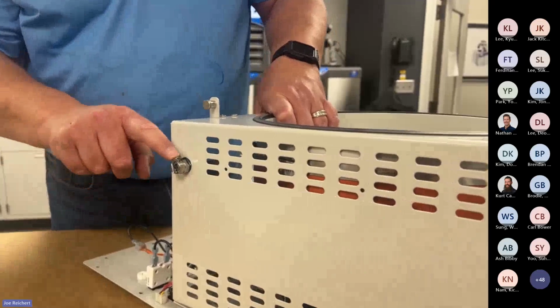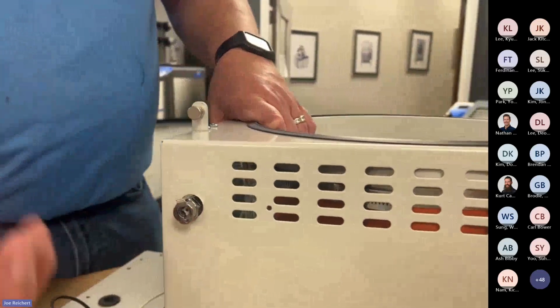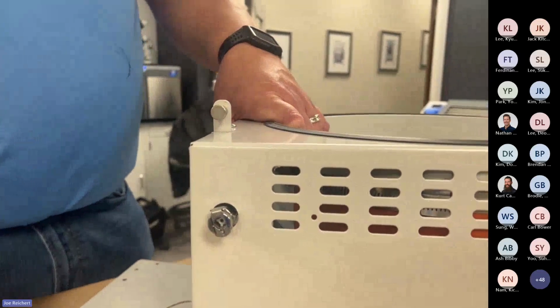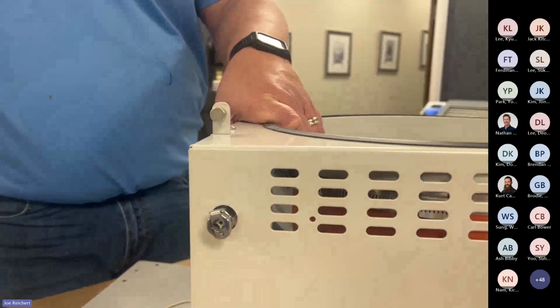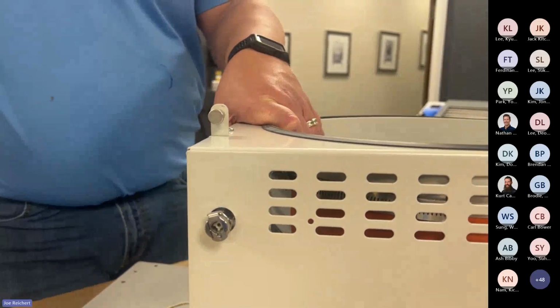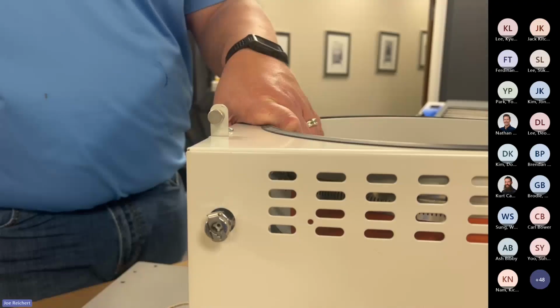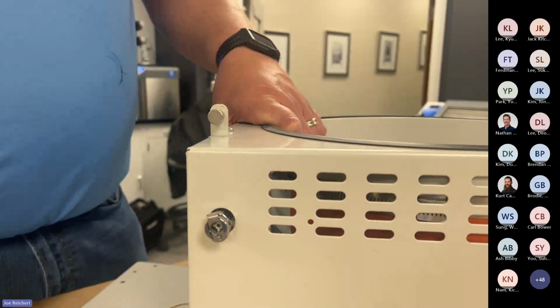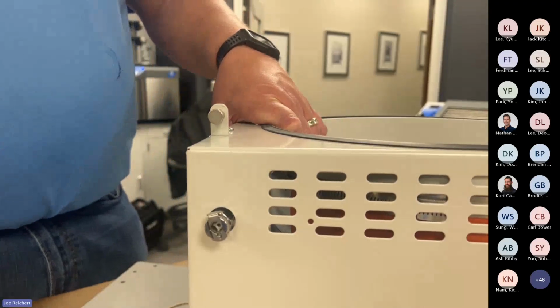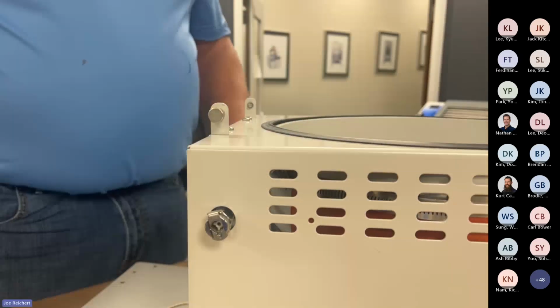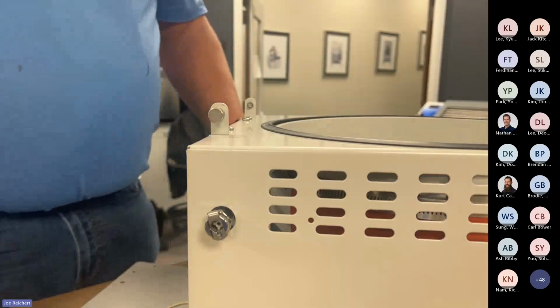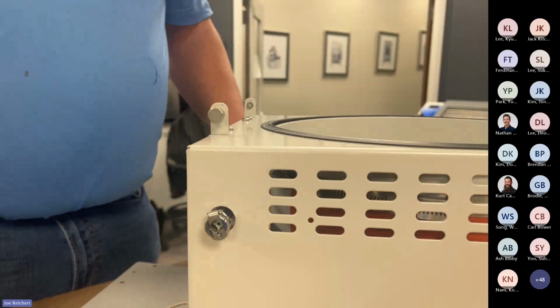You want to pop that out. It's just a little push of the button and the valve comes out of there. But that piece is used for attaching a vacuum gauge if you need it. Or we also have a vacuum controller if you're using a diaphragm pump, and you can control the vacuum with it as well. It has a little dial on it and a gauge, so you can dial in the pressure. You really only need pressure of about 10 to 15 millibar.